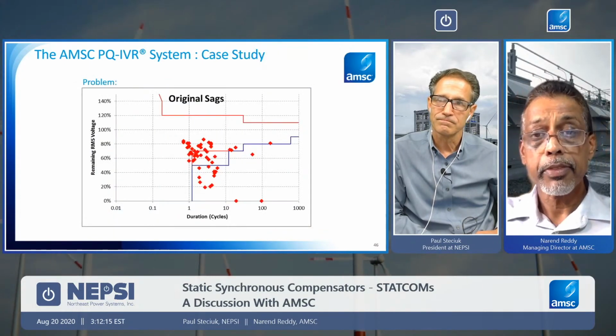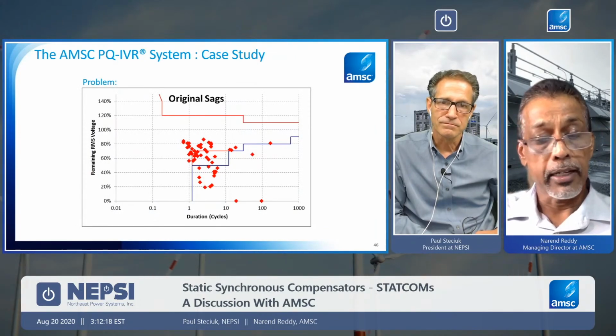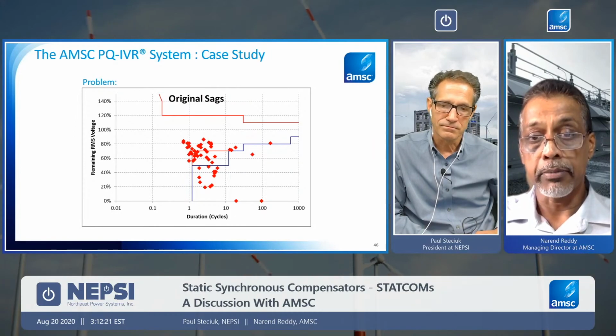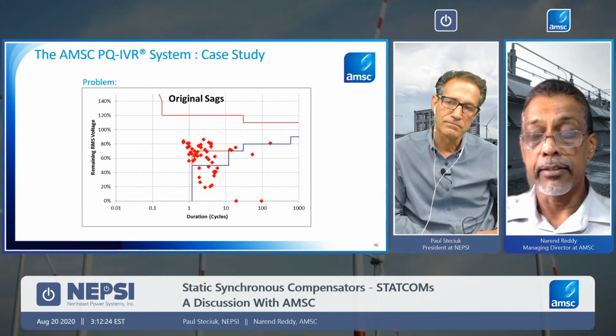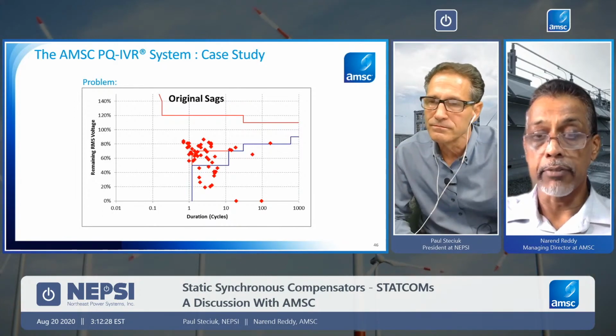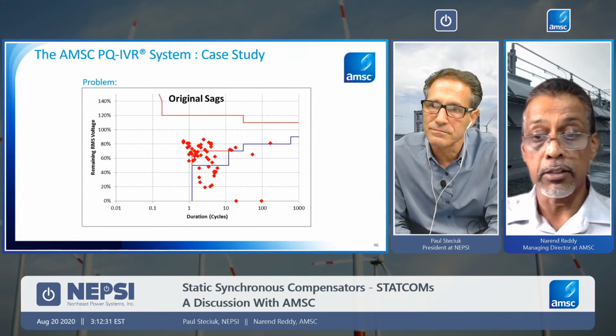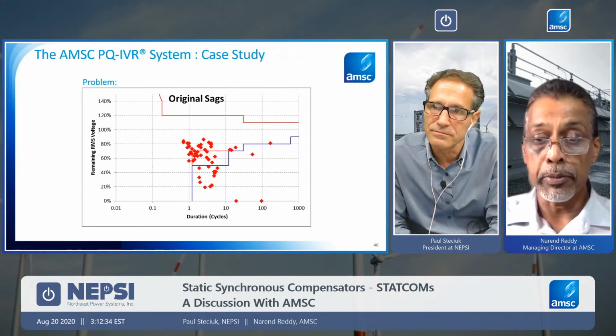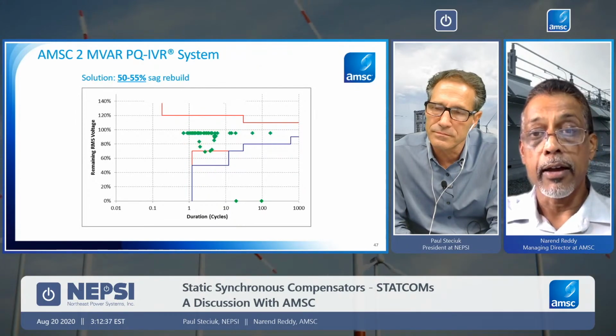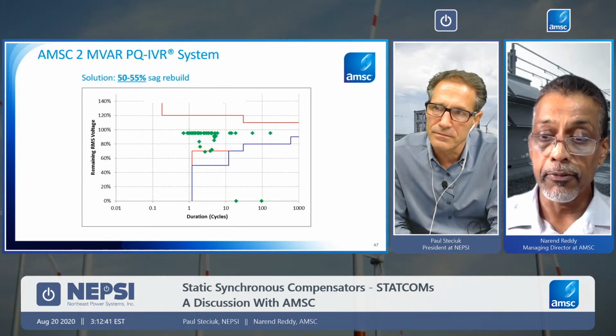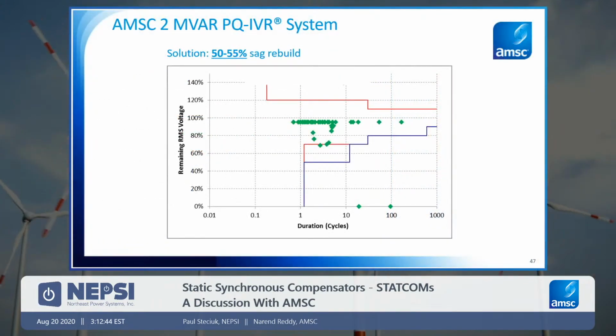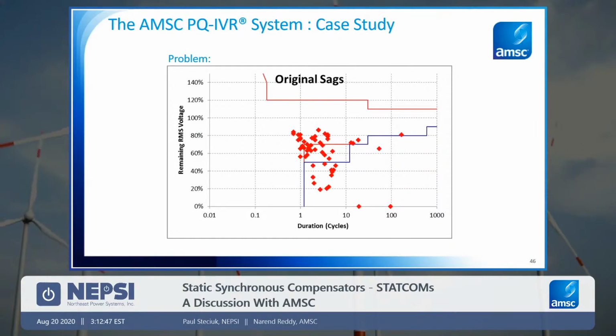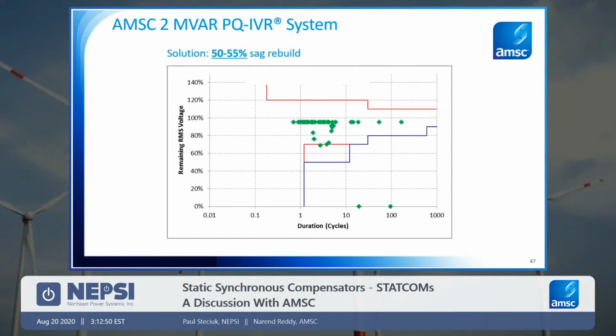So this is giving you an idea. The problem I showed you earlier is what we are solving. We are trying to do data gathering to understand the level of the problem in sags, how deep those sags are, how long they last, and if we did solve it, how many of those we can address for the customer. But really the objective for us is to move this into this region. So as you can see, this is what the problem was, and the solution is to bring those sags up, raising the voltage sufficiently and fast enough so that the system can ride through that fault.